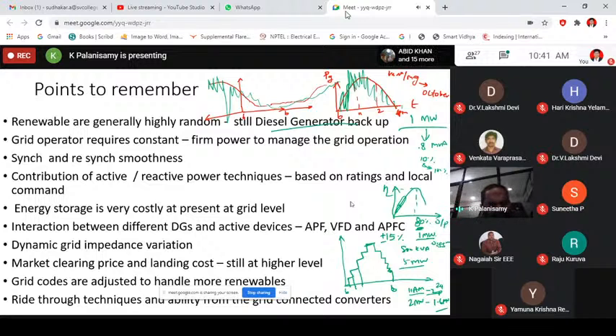So based on the measurement point, the voltage will vary. So definitely, injection or absorption of reactive power should be decided locally, right? Based on the local situation only, you have to take the decision. So your power converter must be intelligent enough to derive the control variable based on the variables of the grid, that is frequency and voltage, right? Then nowadays, because of the phasor measurement unit, or time-stamped values of the grid parameters, right?